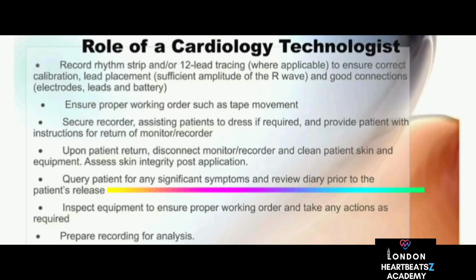Page 10 covers this. The tech often runs a quick baseline recording, maybe a rhythm strip, sometimes even a 12 lead if the system allows. This confirms the leads are in the right spot, the signal looks good, especially checking for a nice tall R wave, which the analysis software relies on. Checking the machine works too. Yep, ensuring it's recording properly, like if it's an older tape model, that the tape is moving. Then securing the recorder comfortably, maybe helping the patient get dressed over it, and giving clear instructions on wearing it, caring for it, and crucially, when and how to return it.